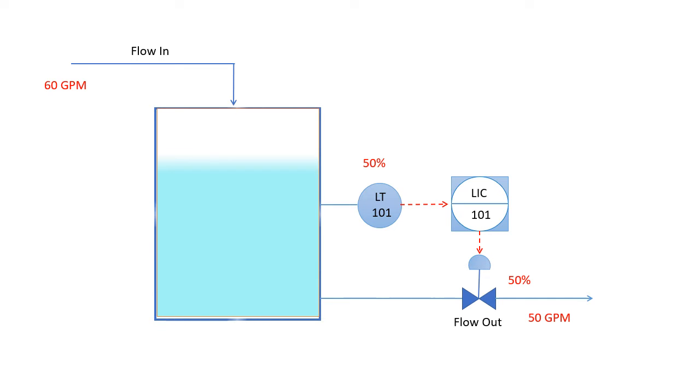Now if the controller gain is 2 percent, 1 percent increase in level would cause 2 percent increase in the valve opening because we know that proportional controller output is gain times error. So when there is a 1 percent increase in level, say 50 to 51 percent, the gain of 2 percent will be multiplied with the 1 and that will cause valve to open to 52 percent.